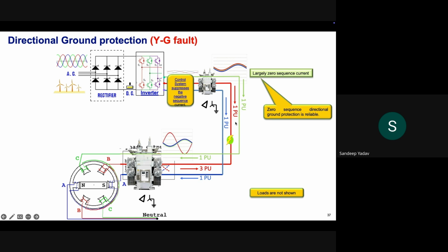So although the fault is in the Y phase, the current in all three phases is 1 per unit, and they all are in phase, because the zero sequence components of fault current in all three phases are equal. So all three currents are equal and in the same phase. It is largely a zero sequence current, and a relay based on negative sequence polarization will not be able to detect this fault. So we need a directional element which works on the basis of zero sequence current. A directional element which operates on the basis of zero sequence current will be able to detect this fault because it is largely zero sequence in nature.